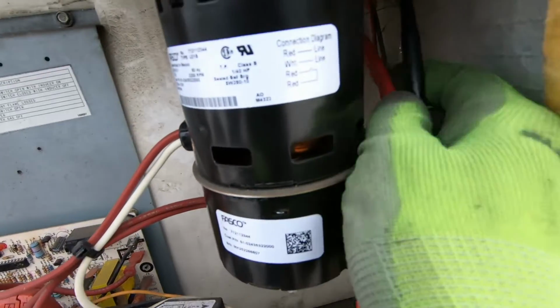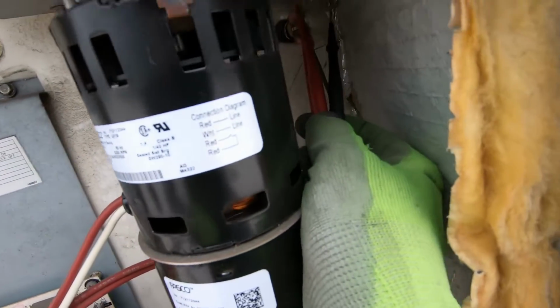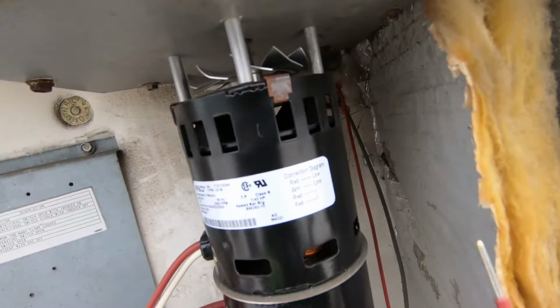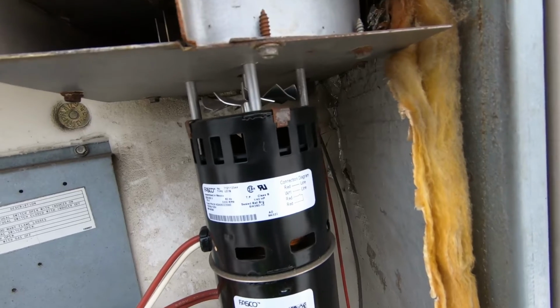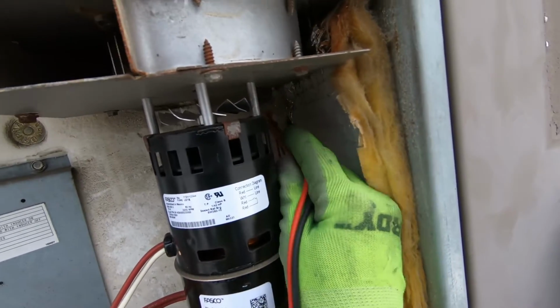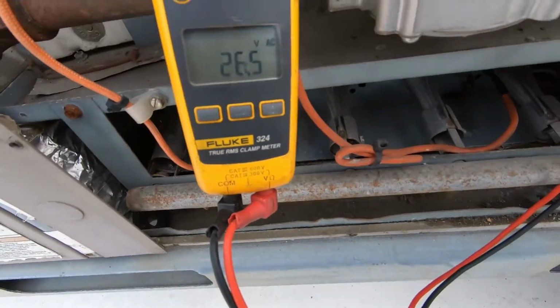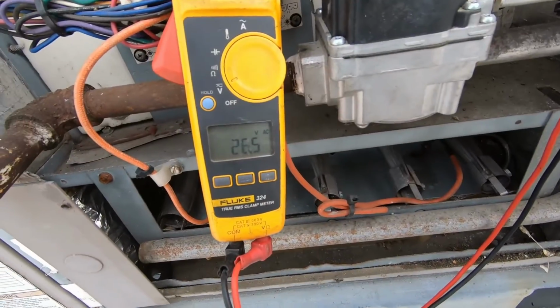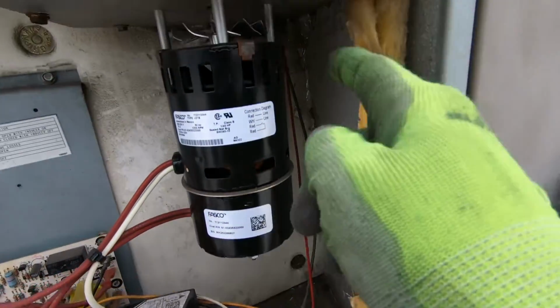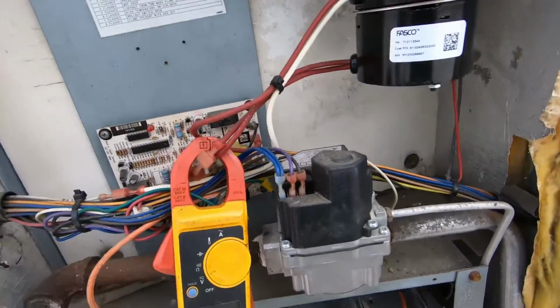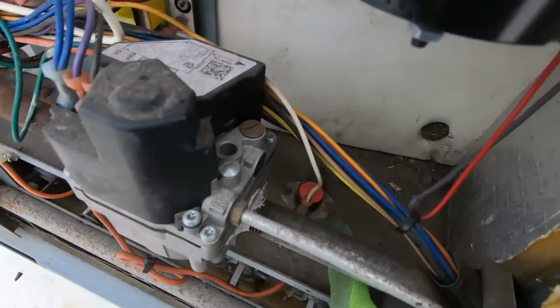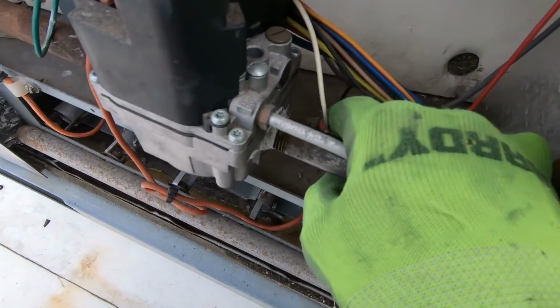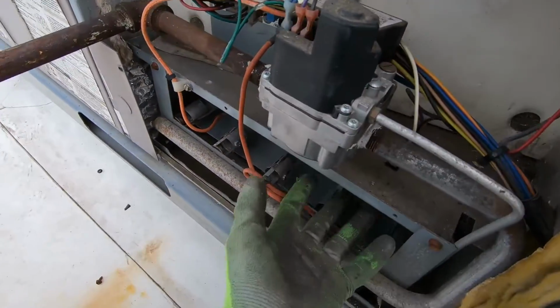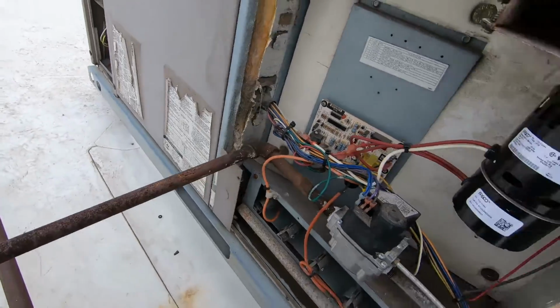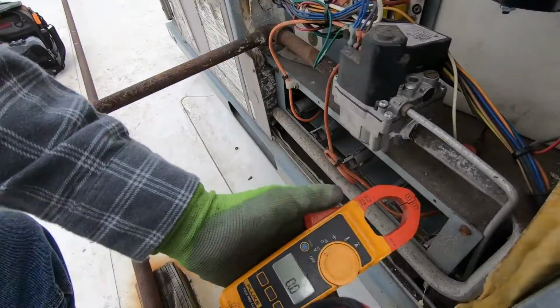All right, guys, so I checked this limit back here and we have voltage on either side. Trying to film this stuff with the camera is quite difficult, but take my word for it. I've got 24 volts to ground on one side and 26 volts to the ground on the other. So I've got voltage running through that switch right there. It's not tripped. I'm gonna go ahead and check my rollout switch right now, and it's right here. That's gonna sense any heat up above the burners. If there's a crack in the heat exchanger and it's rolling out, it will trip that limit.